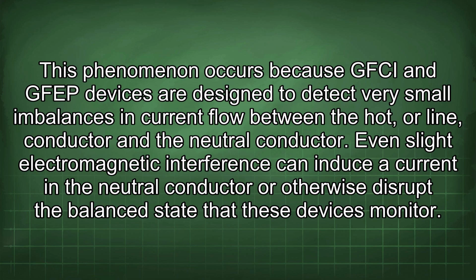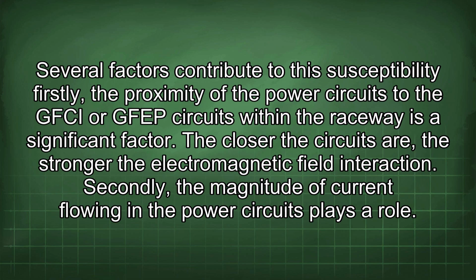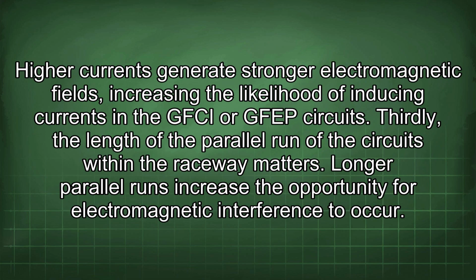Even slight electromagnetic interference can induce a current in the neutral conductor or otherwise disrupt the balanced state that these devices monitor. Several factors contribute to this susceptibility. Firstly, the proximity of the power circuits to the GFCI or GFEP circuits within the raceway is a significant factor. The closer the circuits are, the stronger the electromagnetic field interaction. Secondly, the magnitude of current flowing in the power circuits plays a role. Higher currents generate stronger electromagnetic fields, increasing the likelihood of inducing currents in the GFCI or GFEP circuits. Thirdly, the length of the parallel run of the circuits within the raceway matters. Longer parallel runs increase the opportunity for electromagnetic interference to occur.